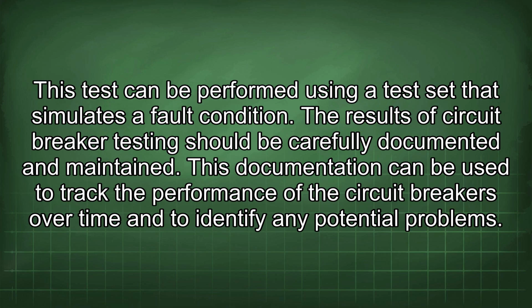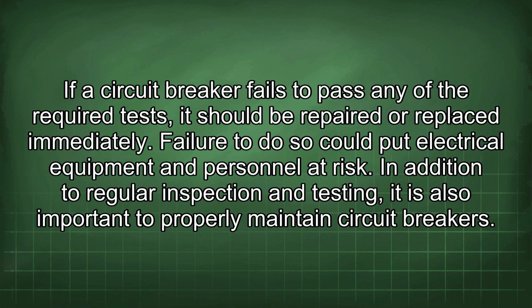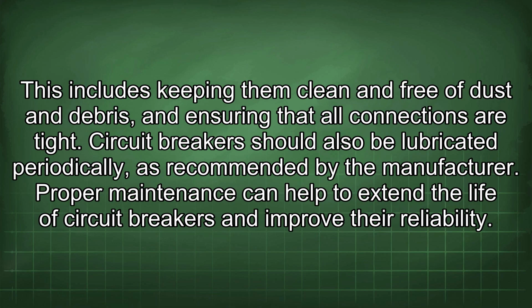The results of circuit breaker testing should be carefully documented and maintained. This documentation can be used to track the performance of the circuit breakers over time and to identify any potential problems. If a circuit breaker fails to pass any of the required tests, it should be repaired or replaced immediately. Failure to do so could put electrical equipment and personnel at risk. In addition to regular inspection and testing, it is also important to properly maintain circuit breakers. This includes keeping them clean and free of dust and debris, and ensuring that all connections are tight. Circuit breakers should also be lubricated periodically, as recommended by the manufacturer. Proper maintenance can help to extend the life of circuit breakers and improve their reliability.